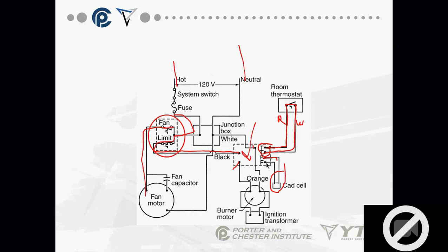Power, sir? Power go up? Yeah, if that limit switch opens, I no longer have power to my transformer. So that display and any programming that's on that thermostat will get lost. This is exactly why I do not like limits on the line voltage side. Because it actually cuts the power out to everything on the control voltage side. Okay? Not the best idea in the world, especially with digital thermostats.